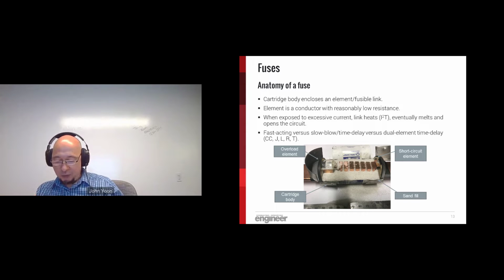So that element is installed within that cartridge body that you see in the picture and is usually surrounded by sand to contain and dissipate that released energy and quench any arc that's formed. Traditional single element fuses are a compromise, either protecting against short circuit or protecting against an overload condition. You can design that single element to melt very quickly and have it be very fast acting, or you can sacrifice the speed and have it be a time delay type fuse. But this is a pretty significant trade-off and is unacceptable when you're trying to protect loads of very high inrush currents like motors and transformers.